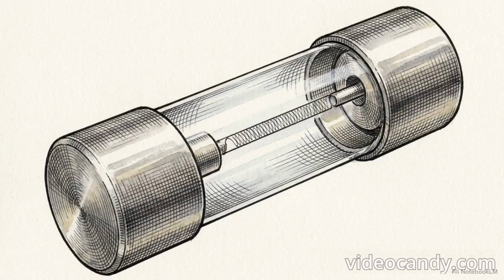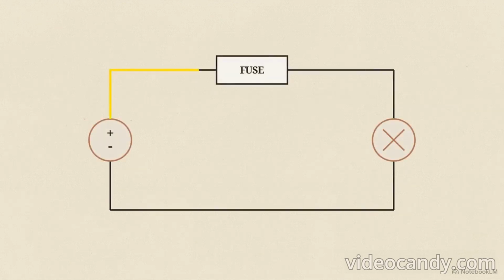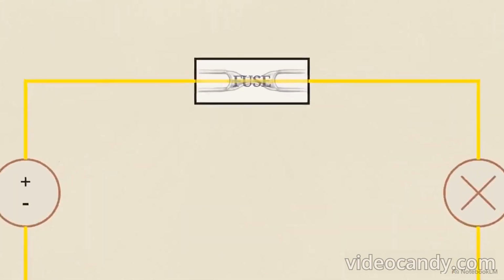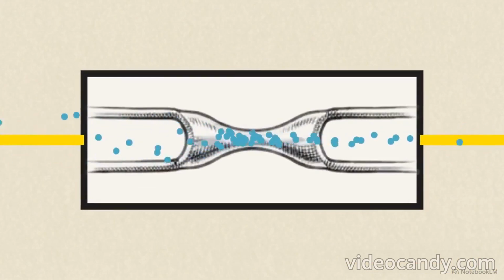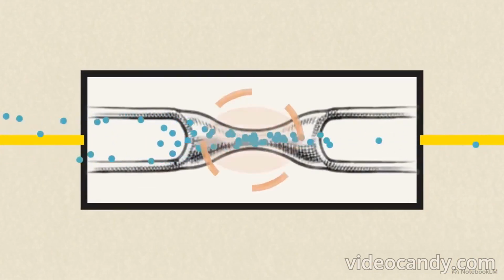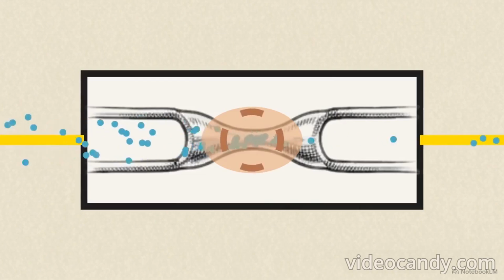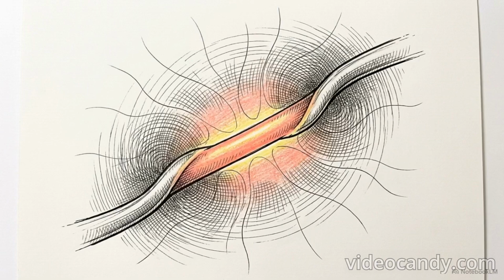The baseline technology for containing runaway current is the sacrificial fuse. Placed directly in series with a load, it serves as an intentional weak link in the electrical chain. The fuse operates entirely on the heating consequence of current. As electrons flow through the calibrated internal metal link, they encounter electrical resistance. The heat generated by this friction is calculated precisely. Power equals current squared multiplied by resistance.